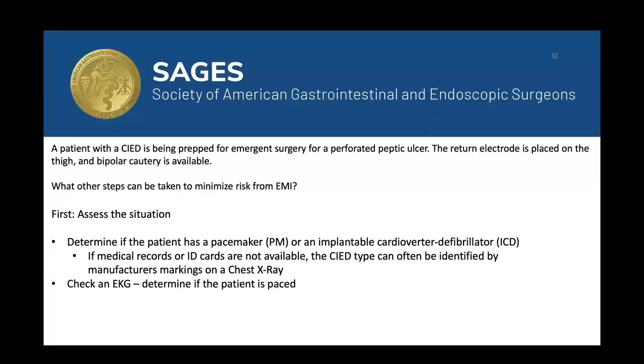So the person needs to go to the OR, but not so fast you can't get an EKG. So get the EKG. You can figure out if the person is pacemaker dependent. And then you can get a chest x-ray or check the patient's records and figure out if this is a pacemaker or a defibrillator. A combination of the EKG, seeing the pacer spikes, and also the appearance on chest x-ray or their records or ID card will help get you there. And so that's kind of the first steps you should do. And I mean, this takes very little time and is absolutely necessary.